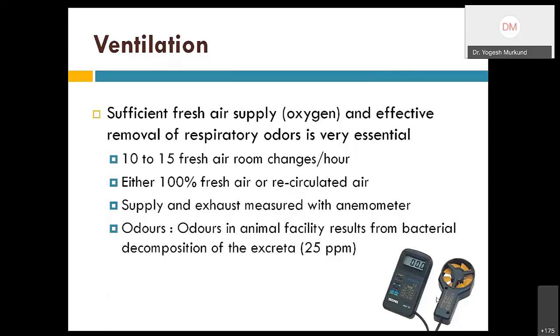Ventilation, normally we say 10 to 15 fresh air room changes per hour are required. 100% fresh air would always be best, but if you have a good HEPA system, you can give recirculated air also. And you should measure this air supply.